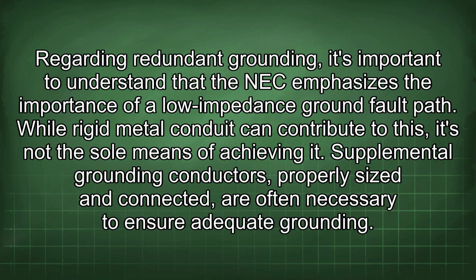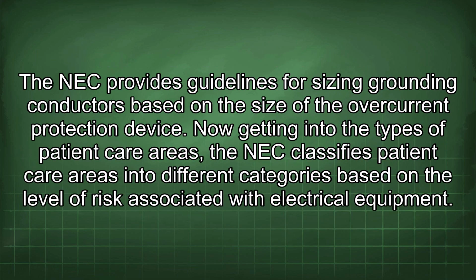Regarding redundant grounding, it's important to understand that the NEC emphasizes the importance of a low impedance ground fault path. While rigid metal conduit can contribute to this, it's not the sole means of achieving it. Supplemental grounding conductors, properly sized and connected, are often necessary to ensure adequate grounding. The NEC provides guidelines for sizing grounding conductors based on the size of the overcurrent protection device.